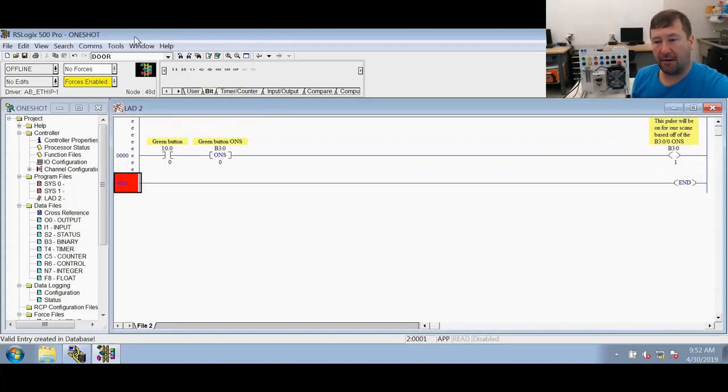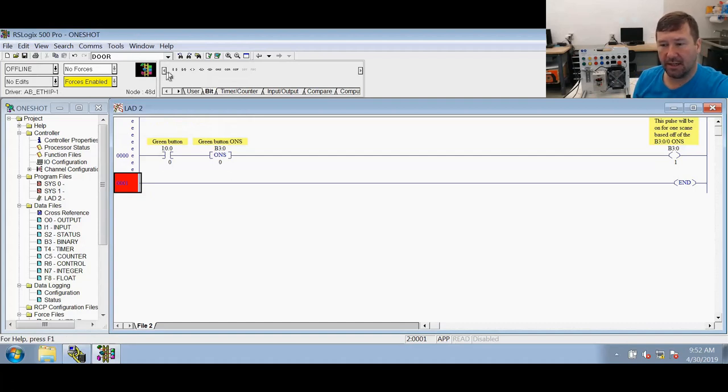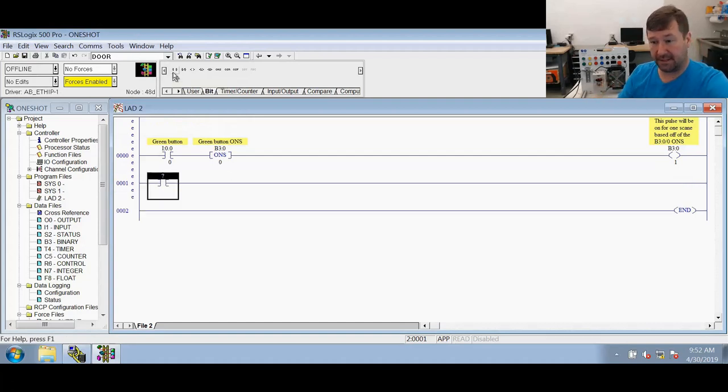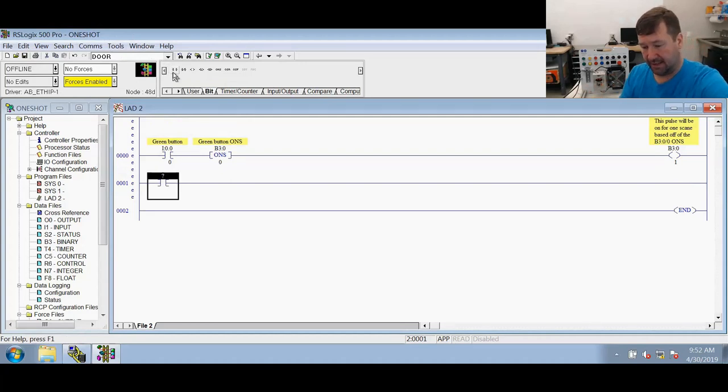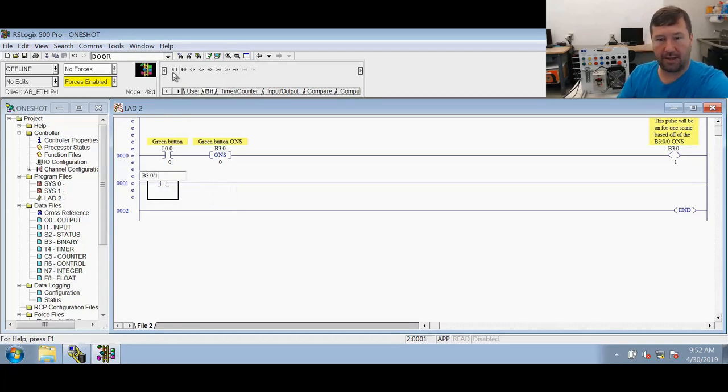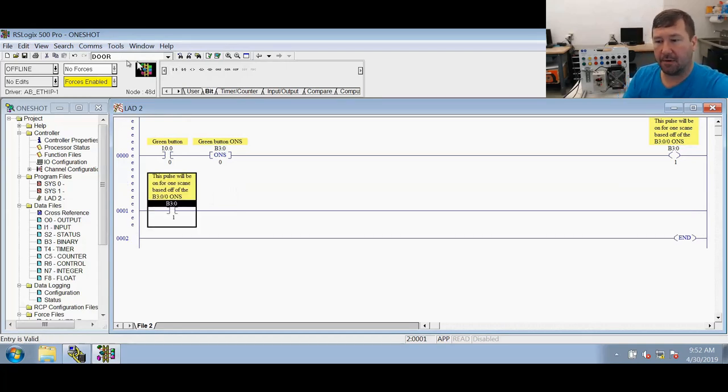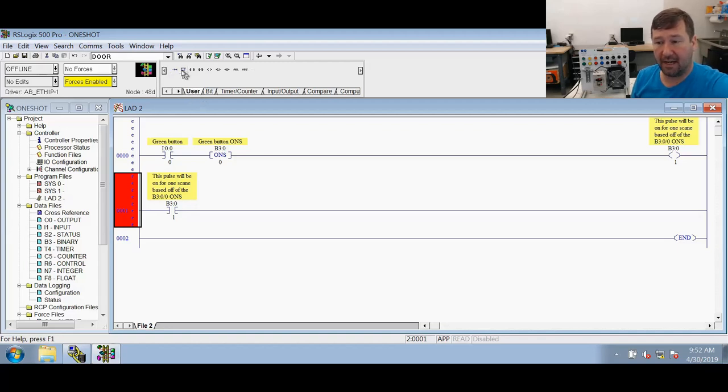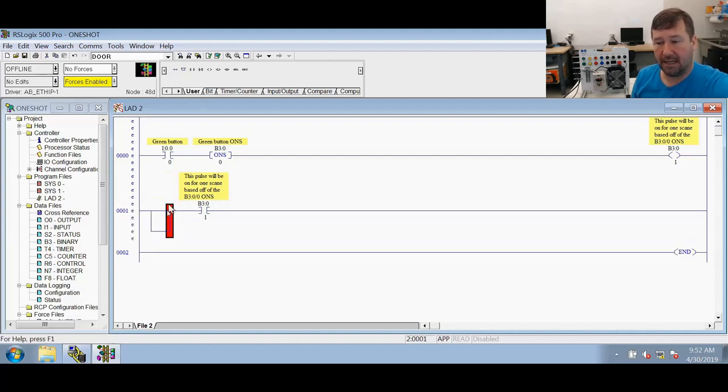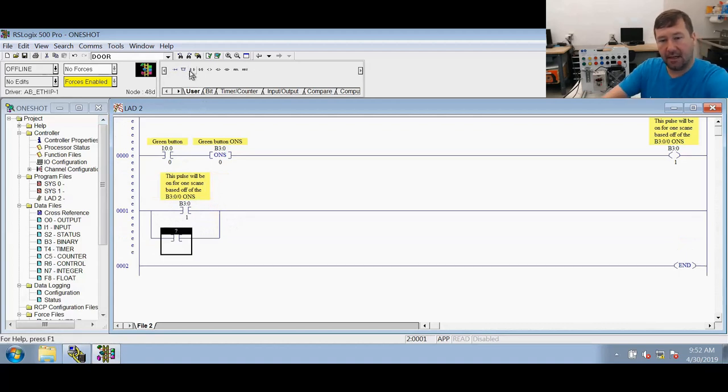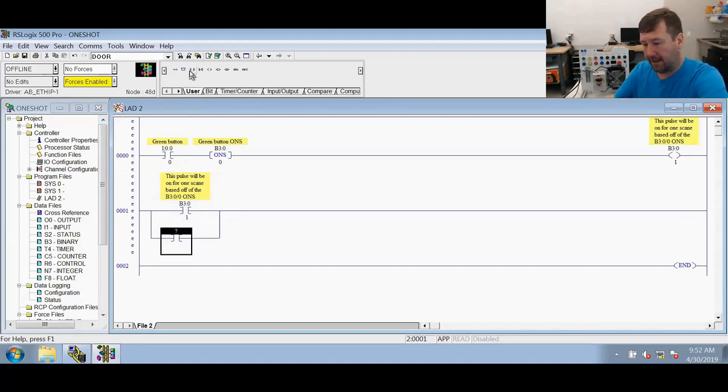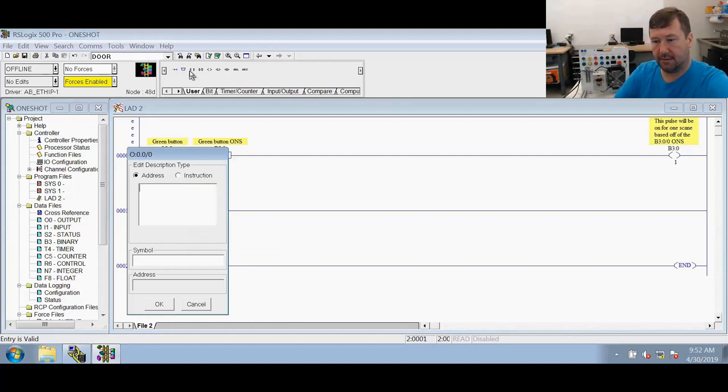All right now we're going to add another rung. And this one we're going to look at that pulse bit that we just added. So that is going to be B3 colon zero backslash one. And we're going to put a branch around it. The branches are on that user tab. Just drag it across there. We'll do an XIC of that green light. The green light is O colon zero backslash zero.